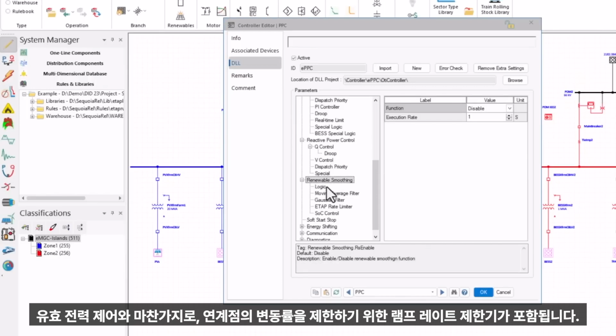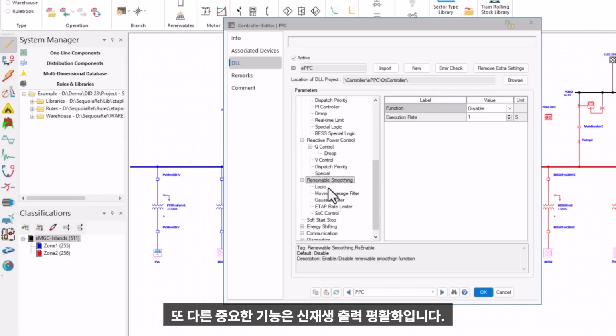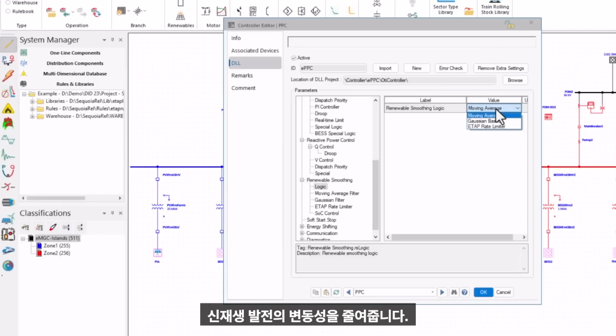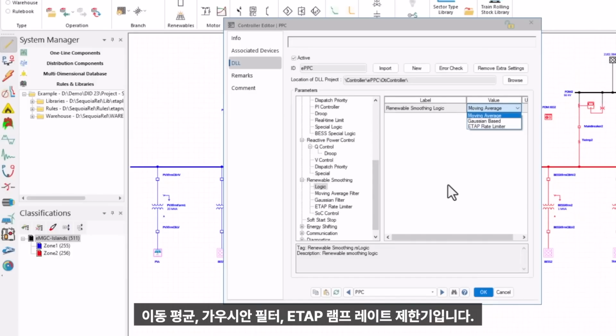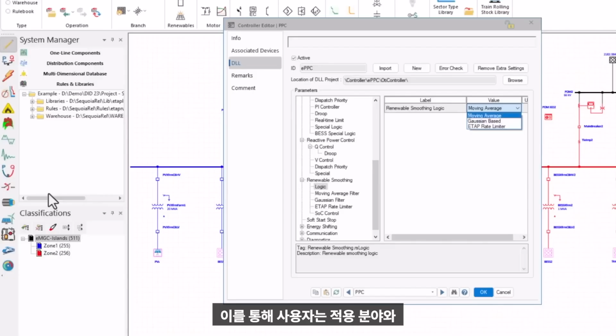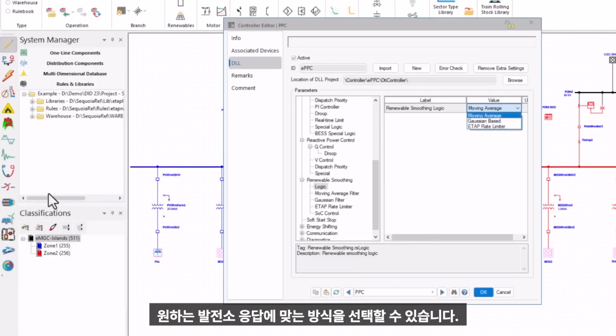Another important function is renewable smoothing, which uses a battery energy storage system, or BESS, to reduce fluctuations in renewable generation. The ePPC offers three methods for this function: moving average, Gaussian filter, and ETAP ramp rate limiter. This gives the user the flexibility to choose the approach that best fits the application and the desired plant response.